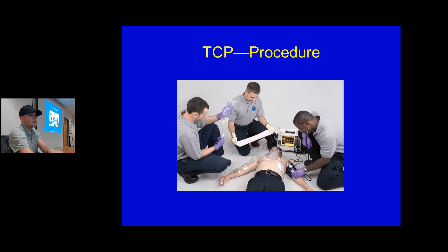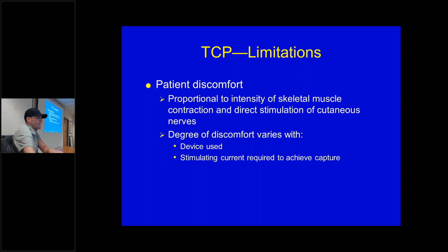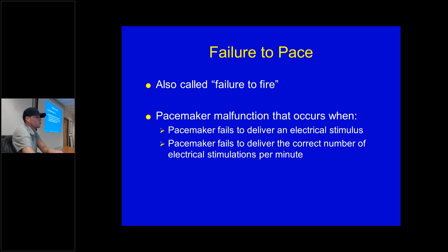All right. So limitations with your transcutaneous pacers. Obviously, they can hurt if the patient wakes up. And it will vary with the current given and the kind of device that is used. There can be failure of your pacemaker, right? Transcutaneous pacemaker. Your leads could be bad. Your pads could be bad. There could be a malfunction in just that aspect of your monitor, and that haven't been checked recently because the patient hadn't been paced for a while, and the pacemaker function just doesn't work. So there can be things that go wrong with it.